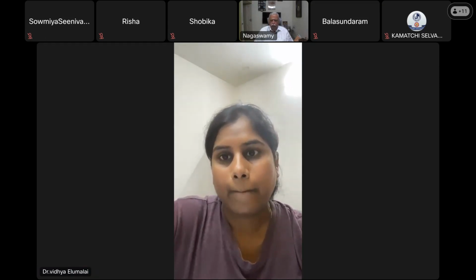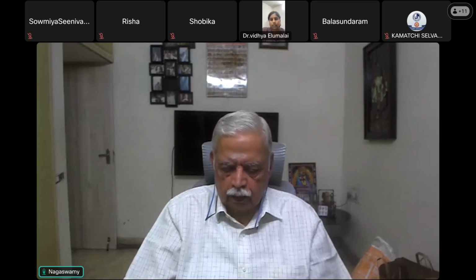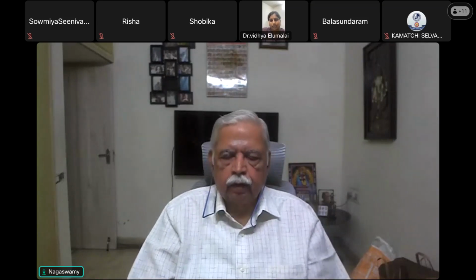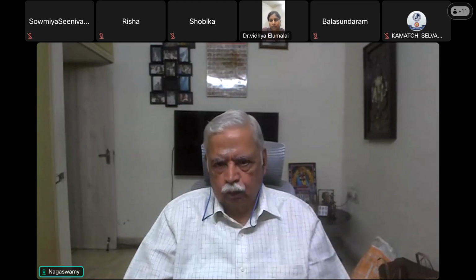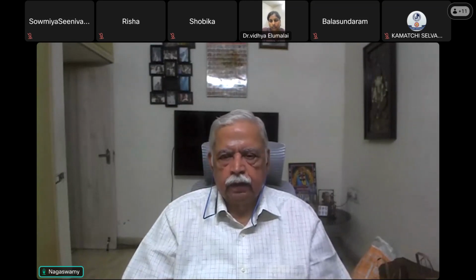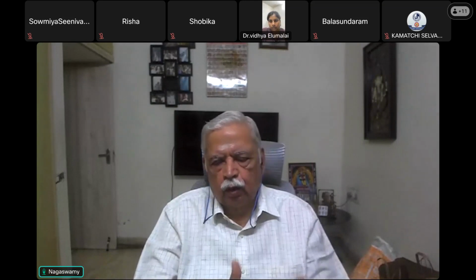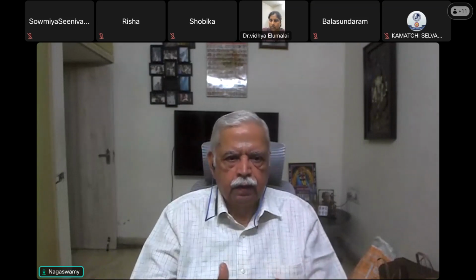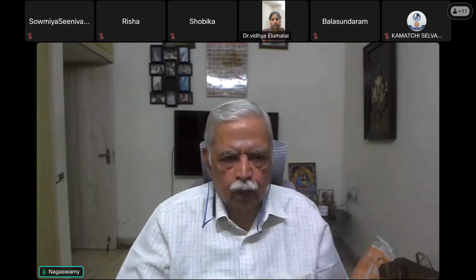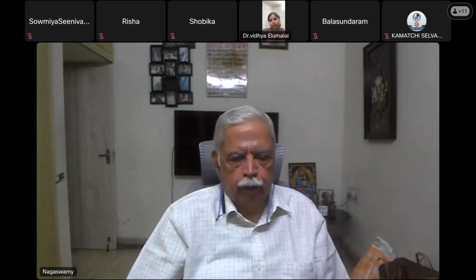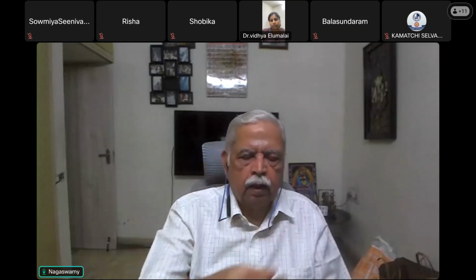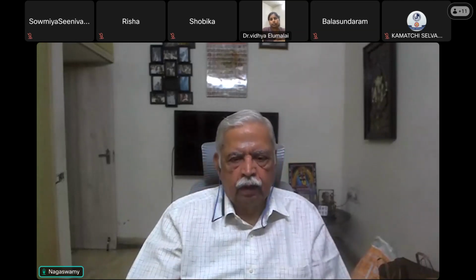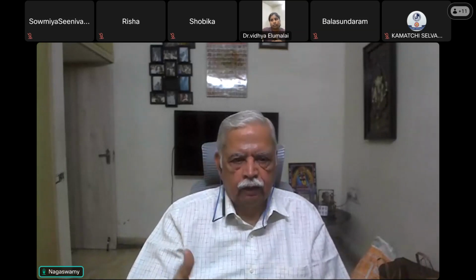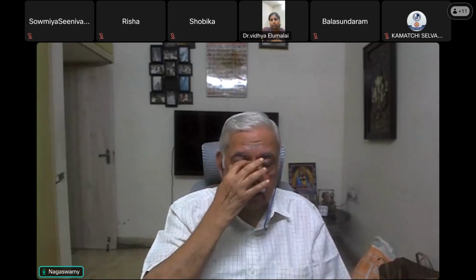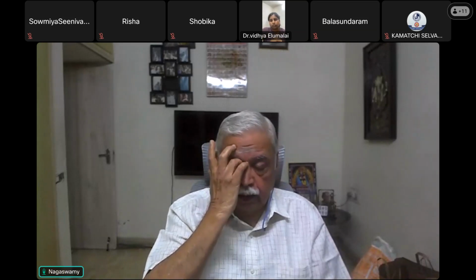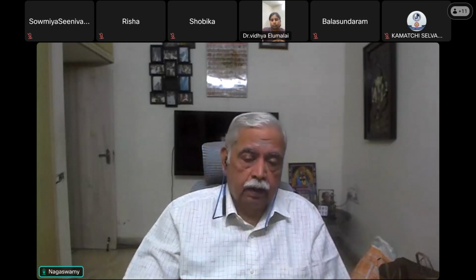Thank you, sir. Very good. A very correct, exhaustive preparation for this. The only suggestion I can give you is that you can divide the checklist into the high pressure system, the intermediate system, and the low pressure system. That way you won't forget each and every point. Starting from the central pipeline to the attachment to the machine, the presence of a spare cylinder is very, very important. And alternate measures of ventilation like an Ambu bag should be present in all theaters.